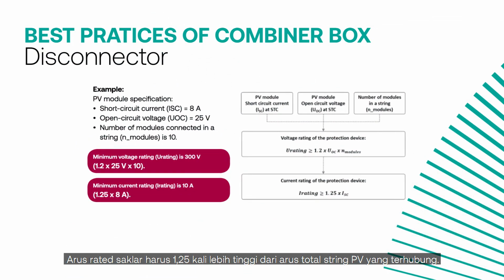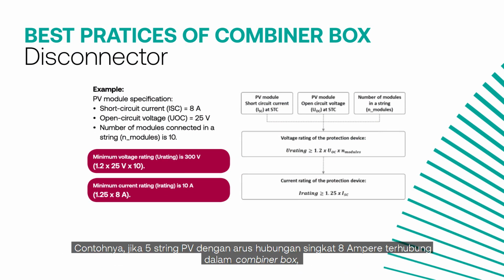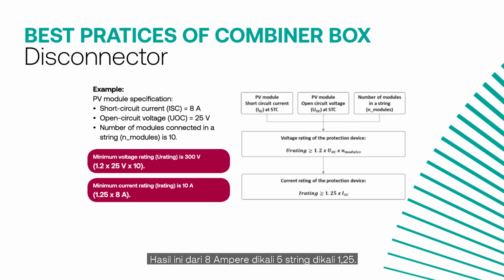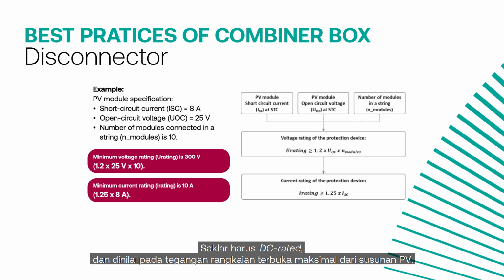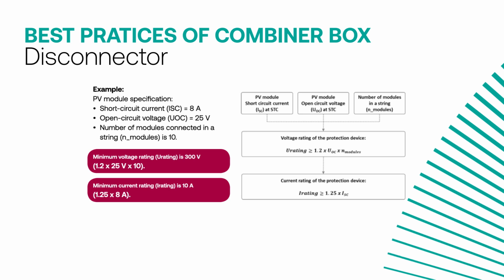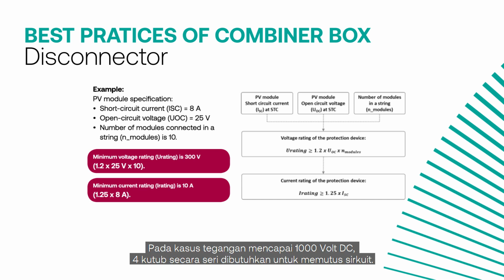The rated current of the switch should be 1.25 times higher than the total current of the connected PV strings. For example, if 5 PV strings with a short circuit current of 8 amperes are connected in the combiner box, a switch disconnector rated at equal or greater than 50 amperes should be used. It comes from 8 amperes times 5 strings times 1.25. The switch should be DC rated and graded at the maximum open circuit voltage of the PV array. In case the voltage reaches 1000 volt DC, 4 poles in series are required to break the circuit.